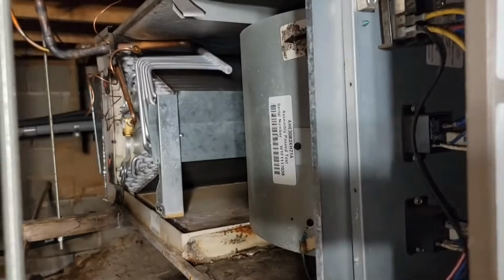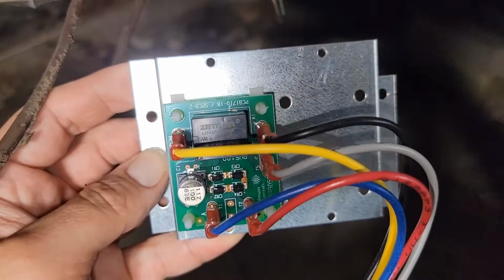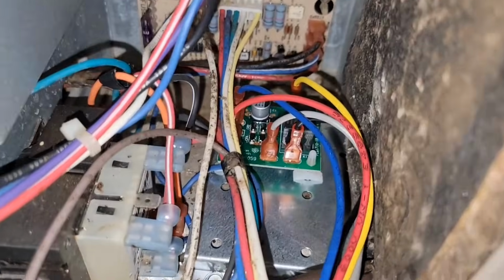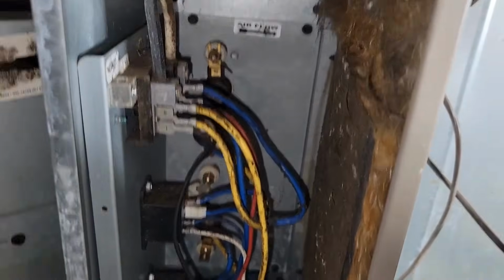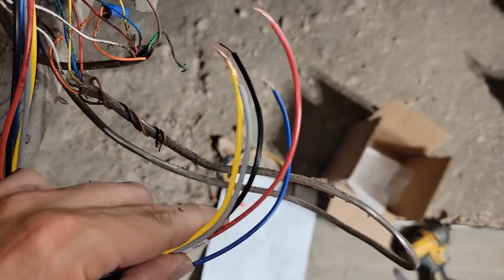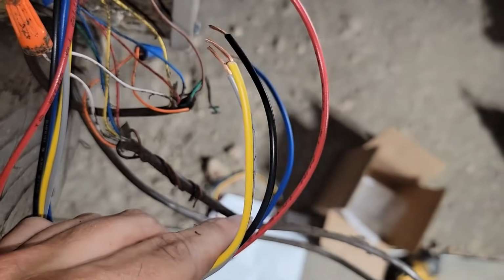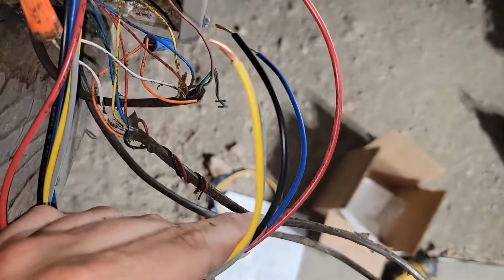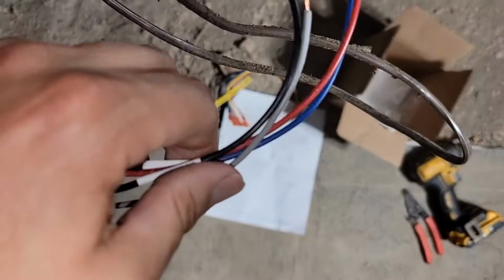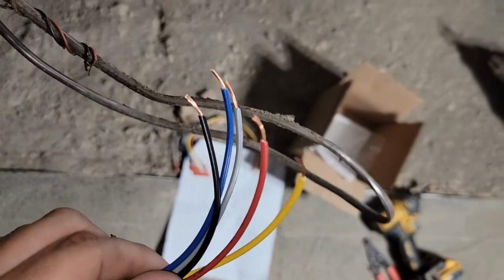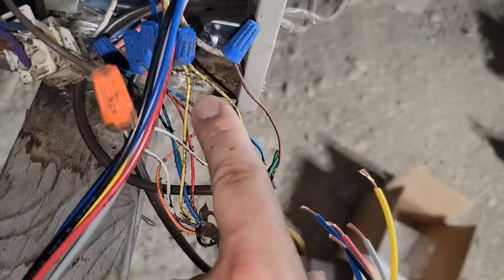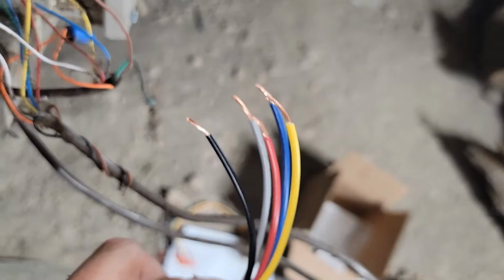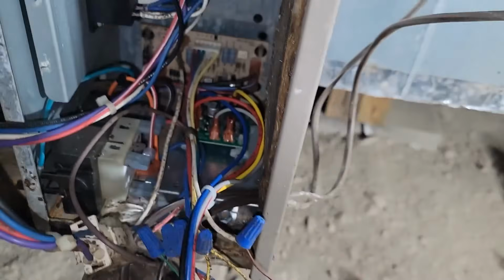Of course, this is not a furnace, this is an air handler. So let's get this board mounted and go ahead and get it wired up. Board is mounted in the bottom of this air handler here, and then I've got the wires leading from that relay board. I cut off all of the ends because I won't use those spade connectors. I will just wire nut these in with my existing thermostat wires. So I'll get it wired and I'll show you how I did it.